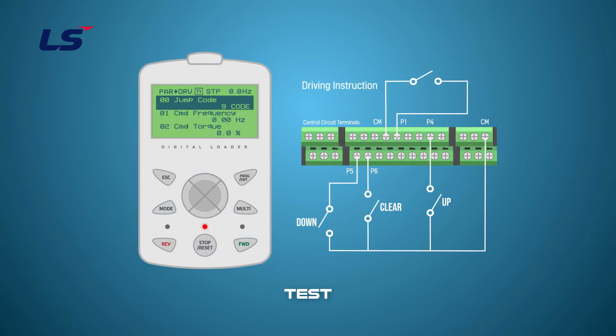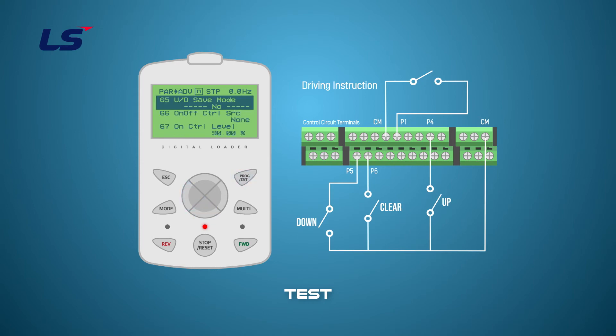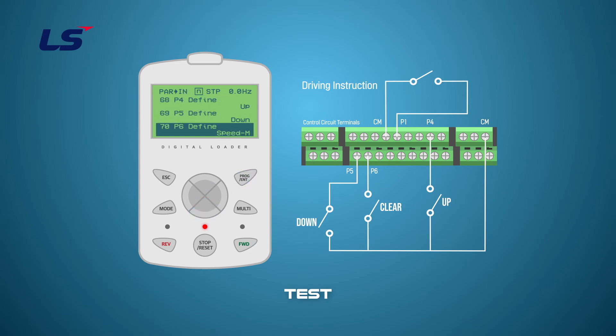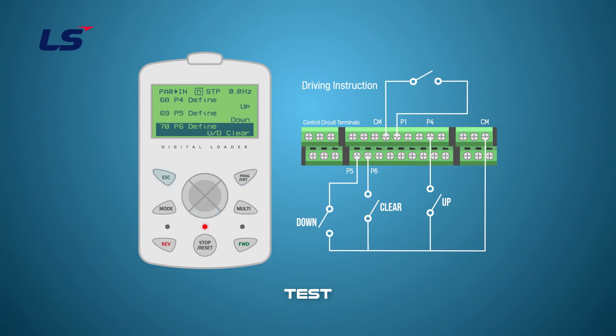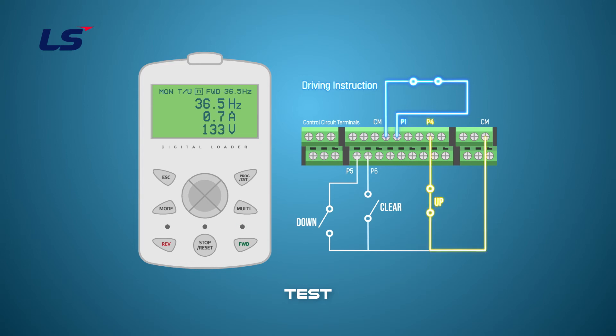Next, let's test the Up-Down save operation. Set ADV 65 Up-Down save mode to Yes. Then program IN-Group 70 to 20 Up-Down clear. When you have finished the programming, initiate the FX digital input by turning it on, then speed up the frequency by setting the digital input programmed as Up to On. When it reaches 60 Hz, stop it by turning off the FX digital input and the Up digital input.